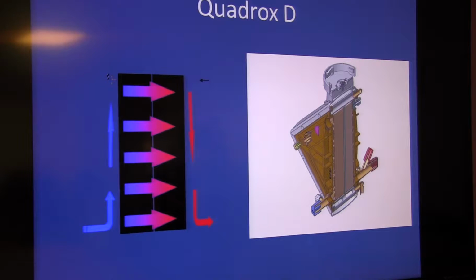And so here's your pump. You've got your patient back here, blood is coming, the pump's got to drive everything. So the pump is the real first physical part of the circuit. And then once you go from the pump, you go to the oxygenator. The way I think about it is, I try to make all of this be as close to reality or as close to what I normally know to have it make sense. So in this case, you have your pump head, you have your oxygenator after it, just like you have your right ventricle sending blood into your lungs.